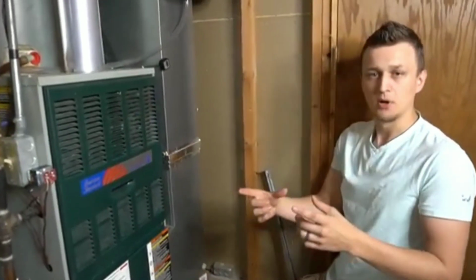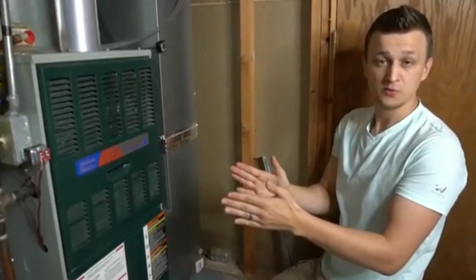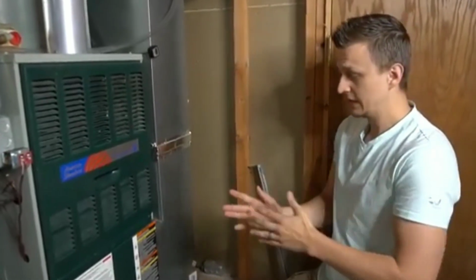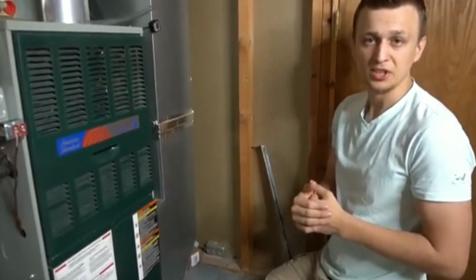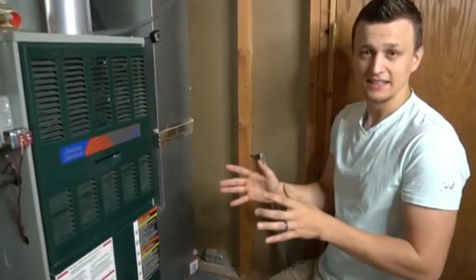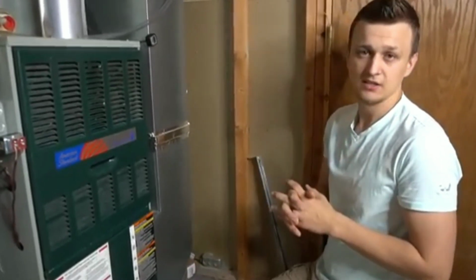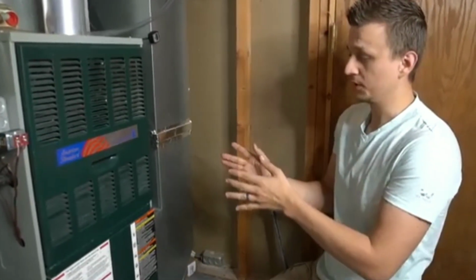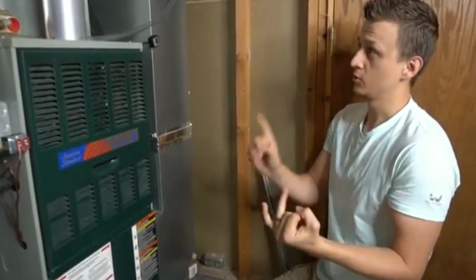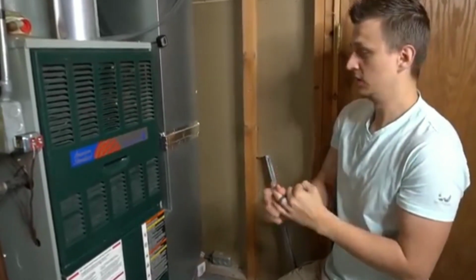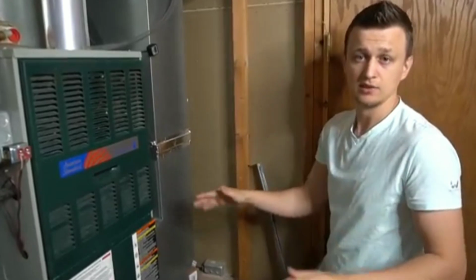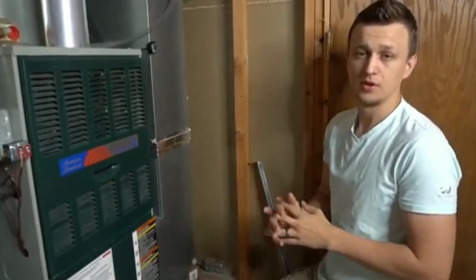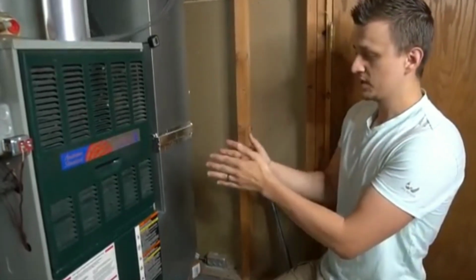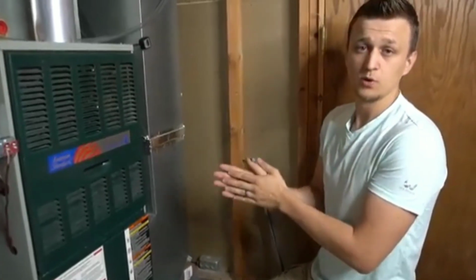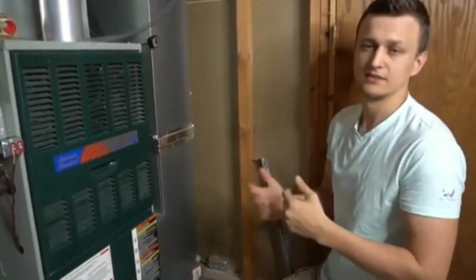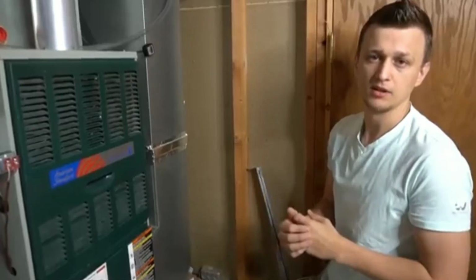And people ask me about the 4-inch filters or the 5-inch filters, those big thick ones. Some of them say that they last up to a year. That's usually not the case. Typically they will not last a year. If you leave them in there for a whole year, your furnace is going to be overheating and your air conditioner is going to be freezing over. Unless you have a spotless house with no dust or anything in it. So those 1-year filters, they do not last 1 year. I would replace them at least every half year or every 8 months.